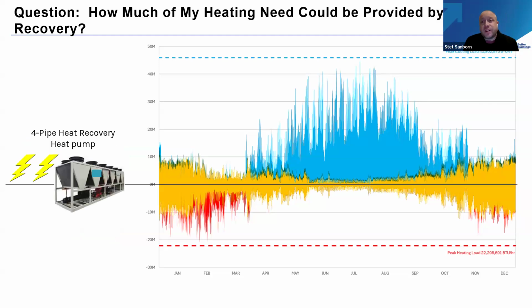So if you are doing a full plant replacement, it might be a great opportunity to switch from a traditional split chiller plus boiler and actually look at what we call a 4-pipe heat recovery heat pump. These are air-cooled pieces of equipment, or air-heated pieces of equipment, that can do both cooling, heating, and simultaneous heating and cooling at the same time. So all of those hours are covered with a single piece of equipment.